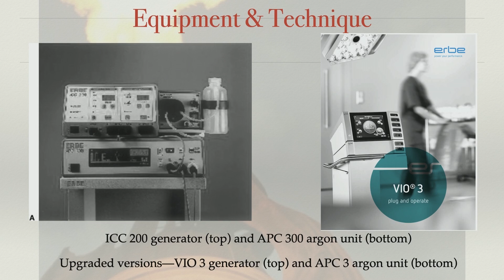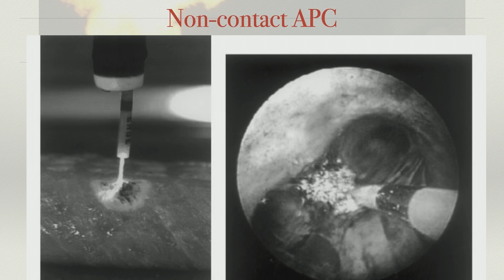So this is basically the equipment. What you see on your left is the older APC and electrocautery machines by Erbe, and now it's much sleeker, more standard, with more software and better hardware than before, and that is the VIO 3 machine with the APC 3 argon unit. And again, like I was telling you in a couple of slides before, this is a non-contact method. So see the picture on the left. You require that gap for the transfer of energy. So if you don't give that gap, that energy transfer does not happen, and therefore you will not be able to get adequate hemostasis. So non-contact method, minimum distance 10 millimeters.